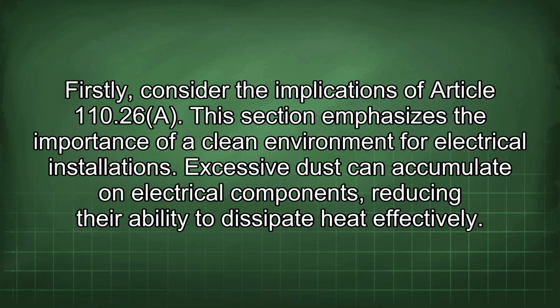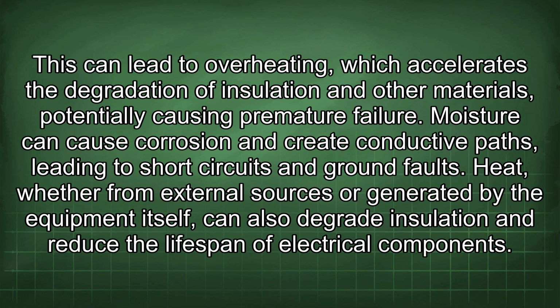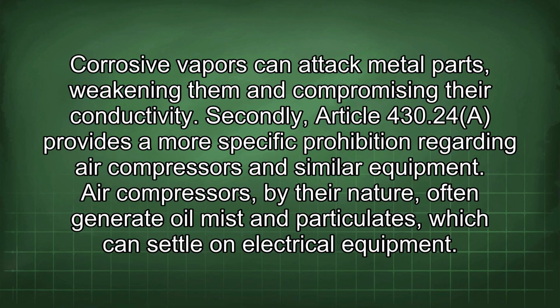Firstly, consider the implications of Article 110.26(A). This section emphasizes the importance of a clean environment for electrical installations. Excessive dust can accumulate on electrical components, reducing their ability to dissipate heat effectively. This can lead to overheating, which accelerates the degradation of insulation and other materials, potentially causing premature failure. Moisture can cause corrosion and create conductive paths, leading to short circuits and ground faults. Heat, whether from external sources or generated by the equipment itself, can also degrade insulation and reduce the lifespan of electrical components. Corrosive vapors can attack metal parts, weakening them and compromising their conductivity.